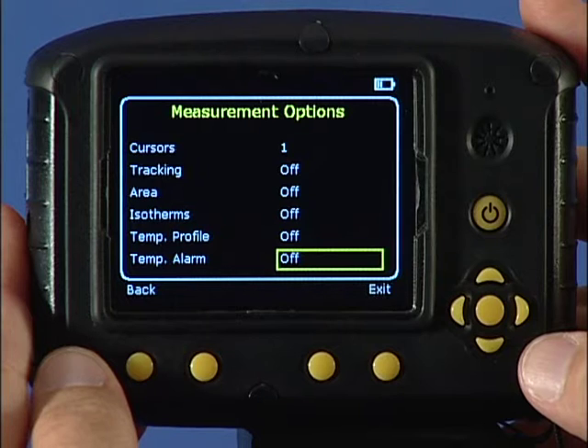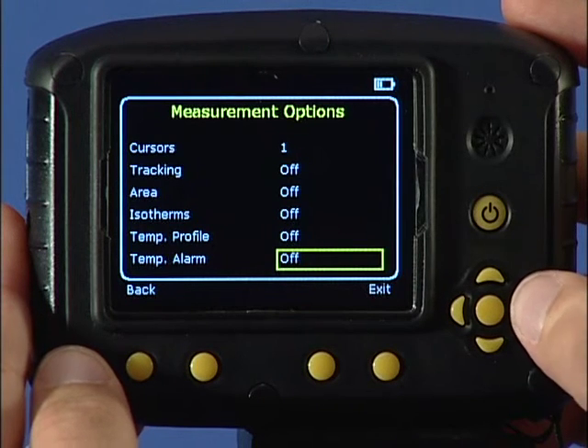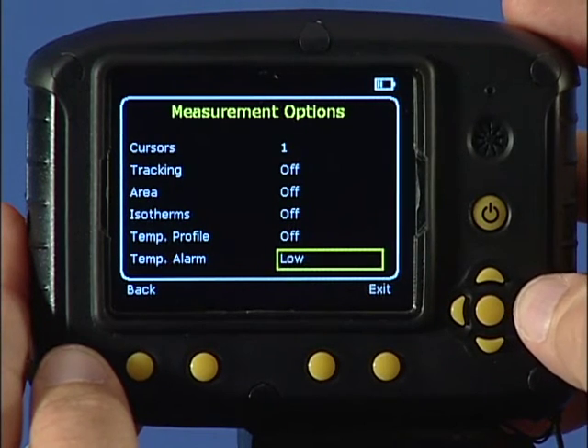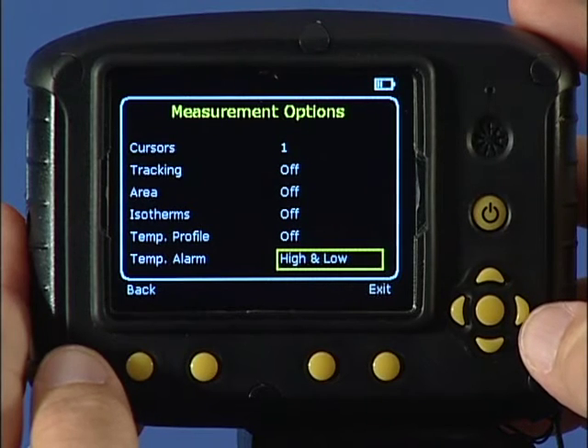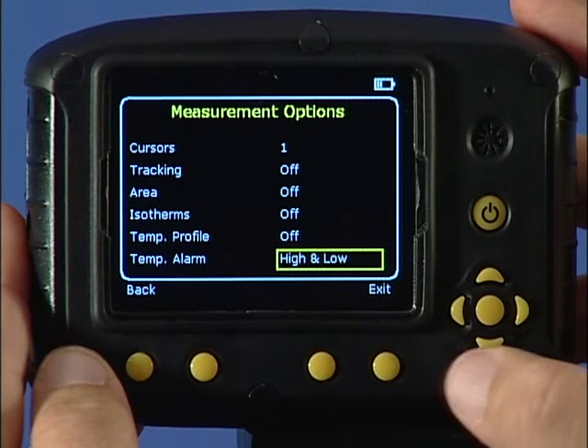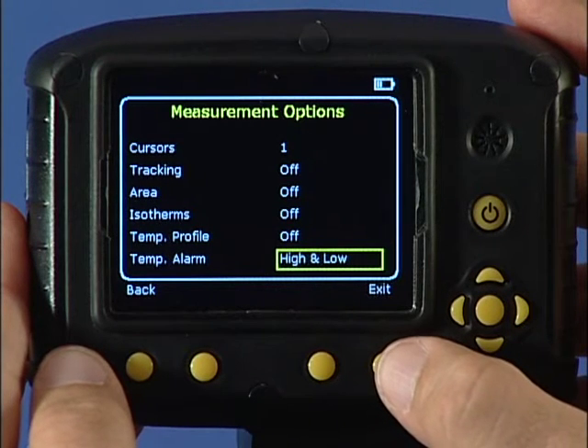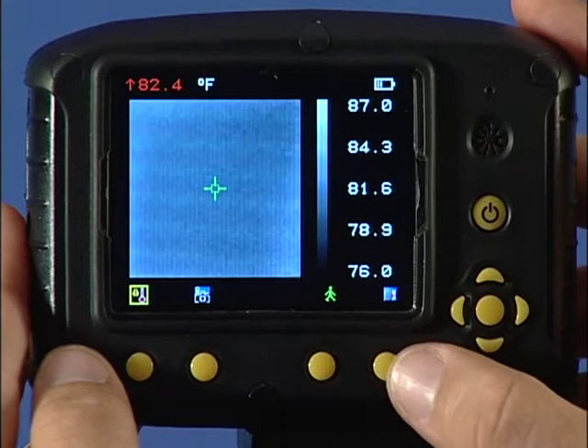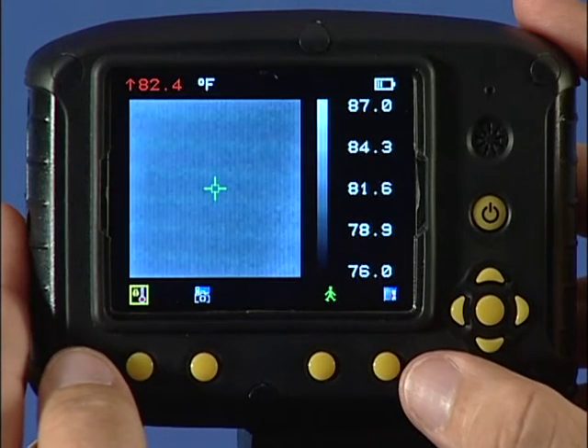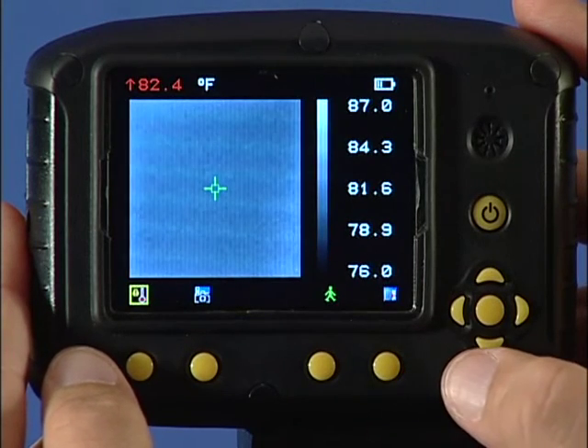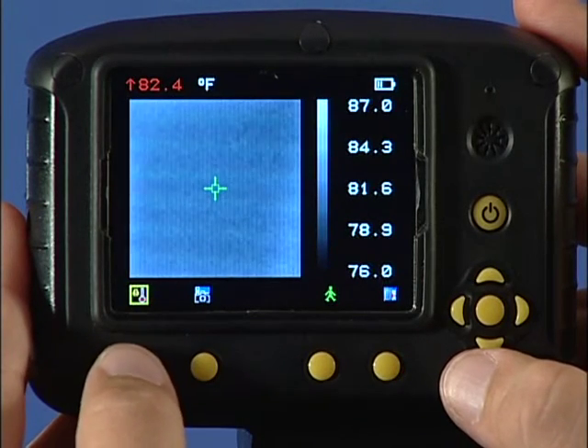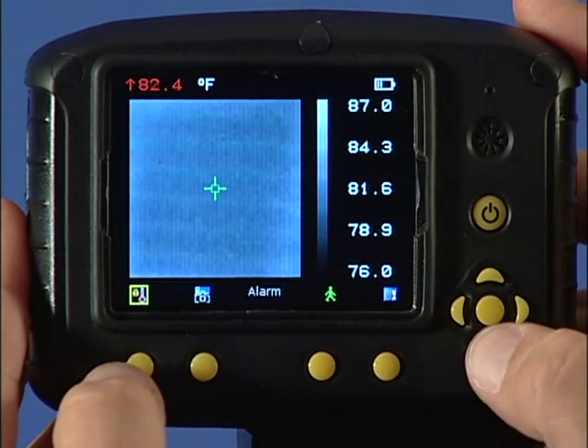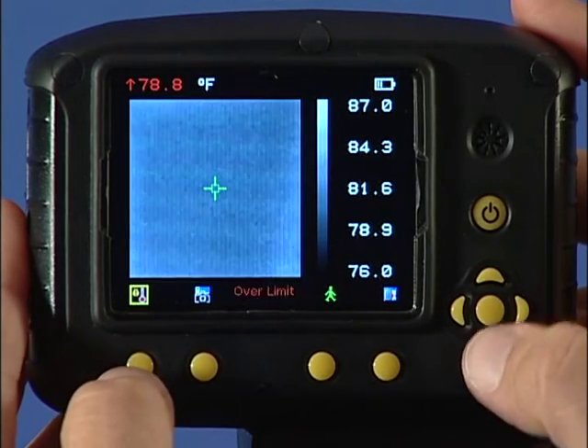The last selection in this menu allows the selection of high, low, or high-low visual and audio alarms to be triggered if either cursor or a point within the designated area is higher or lower than a set temperature. Use function key 1 and the navigation keys to adjust the temperature settings.